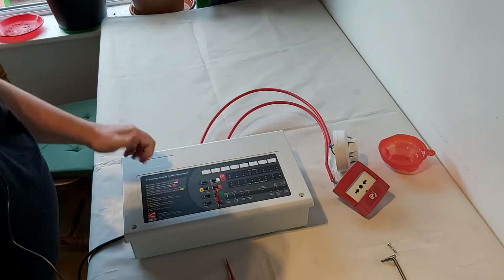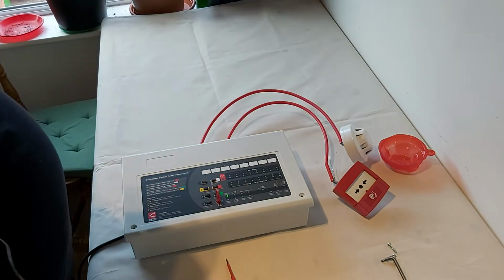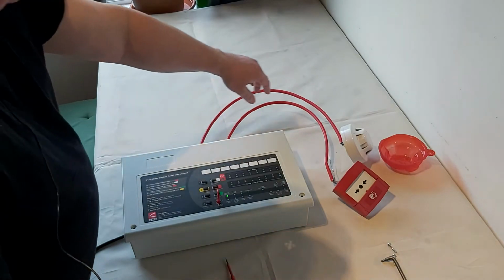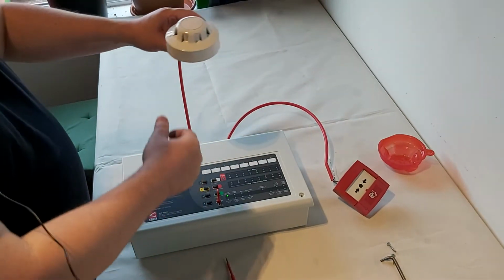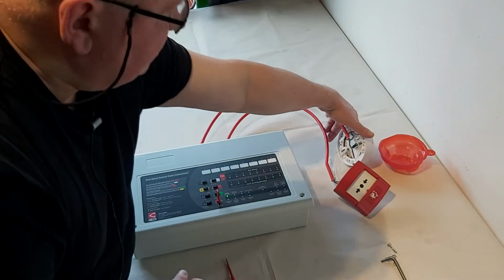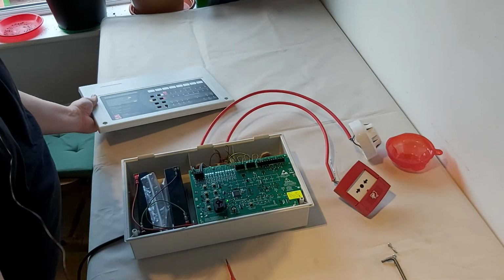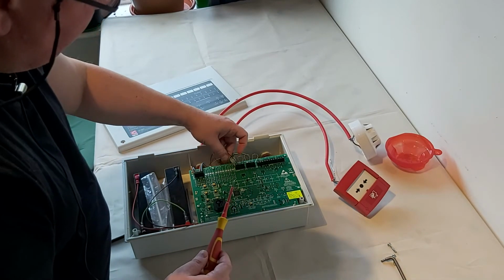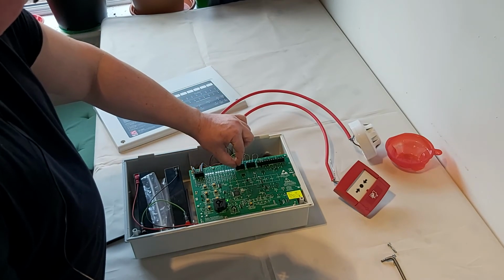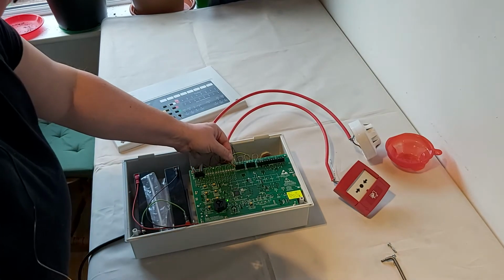So we saw the mains fault, power supply fault, device fault. There could also be other types of faults on cables. Each line of detector or siren will have an end of the line device. And just to make it easy, I will remove end of the line device on one of the sounder lines. There's 4 of them. This one is connected. There's end of the line. Obviously it should be on the end, but because siren is directly connected here, I just have it here just because it's easy, but this should be in the device.